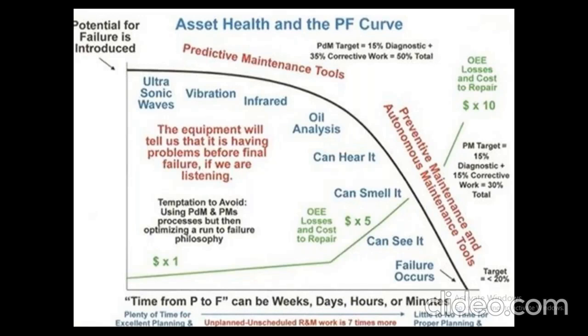The potential for failure, you cannot spot it with ultrasonic, because it is still in the nascent state. At least with infrared, whatever hotspot is seen in the machine, you try to take control and take immediate action. Nipping it in the bud is more important, especially when you correct the defect. If a system has a defect that is originating from a small size to a bigger size and it is nipped in the bud immediately, definitely energy saving is possible in that system. If you allow the defect to grow in the system, energy saving is not possible, only energy cutting will happen.